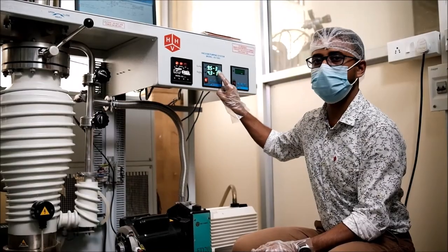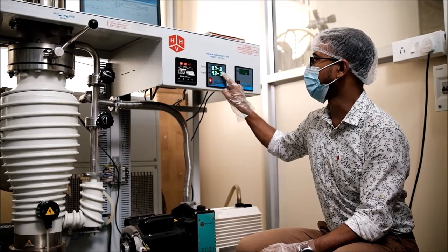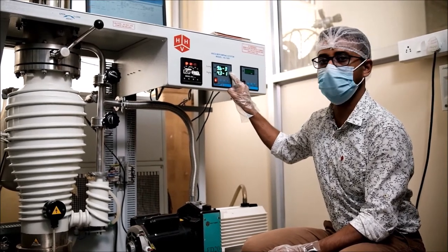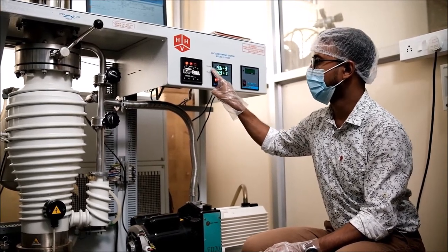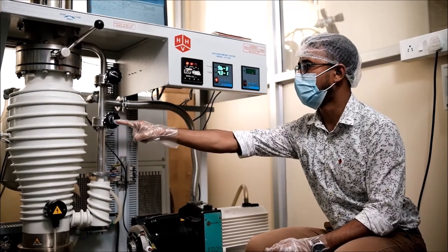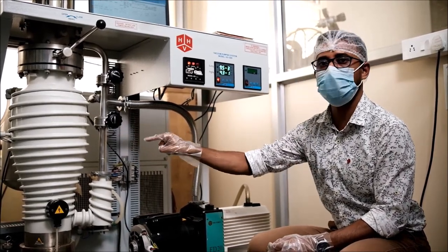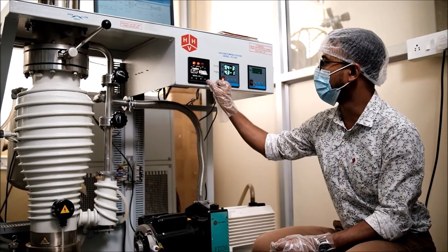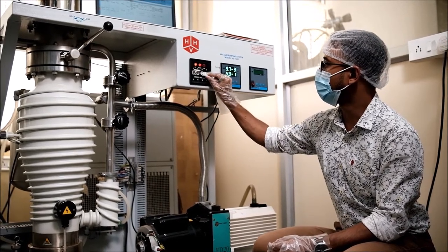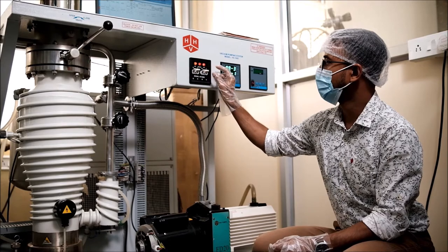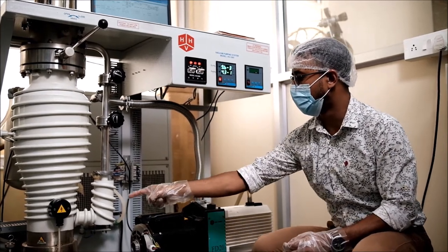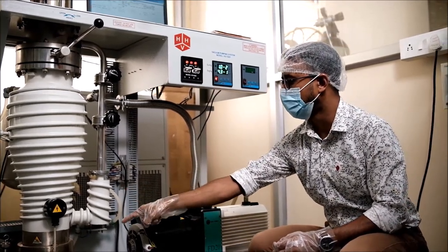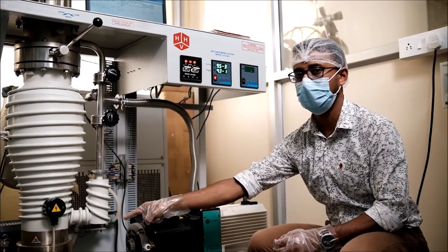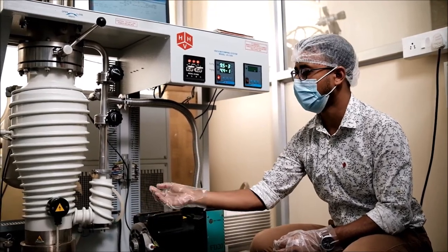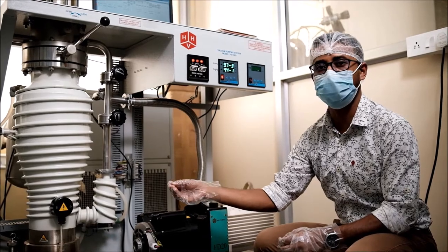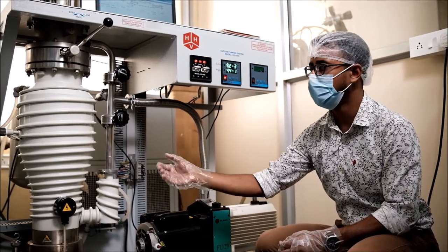Now the backing pressure has reached 10^-3 millibar. The backing pressure means the pressure of the diffusion pump chamber. So now we are ready to turn on the diffusion pump. So we'll do that. This will power up the diffusion pump. That means now the diffusion pump oil will start to heat up, and it takes around 45 to 50 minutes to fully heat up.